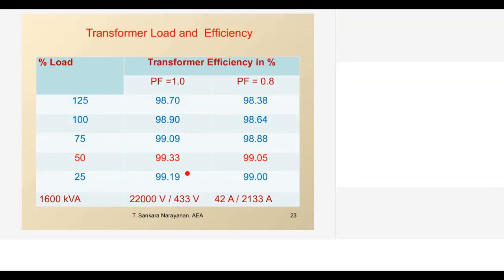That is what the auditor has to do, because some industries will have 10 transformers, some will have 50. Once we put a power analyzer on for 24 hours, we can know the hourly load variation and hourly loss for each transformer. So loss accounting will be better. We will not show a very high loss in a transformer, because when you say distribution loss is 8%, definitely the finance person will ask why 8%, whether the transformer is inefficient. So for loss accounting, we need to calculate all these things.